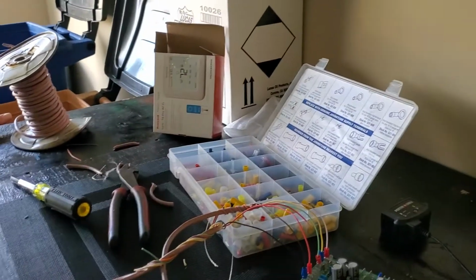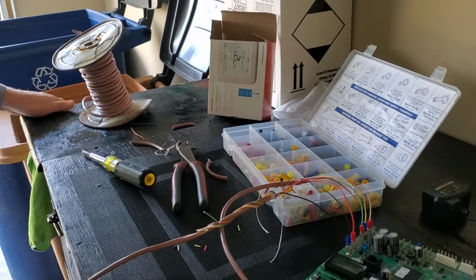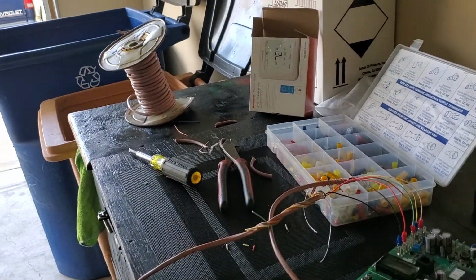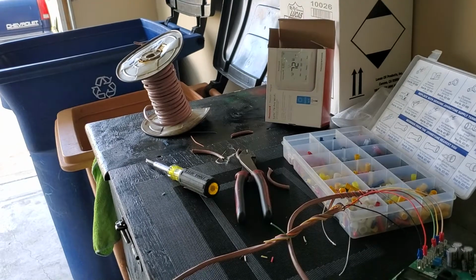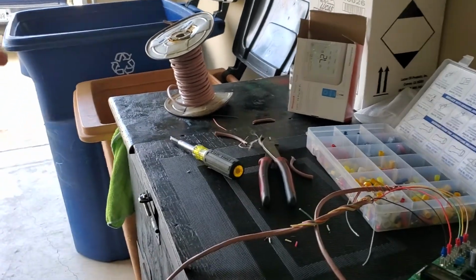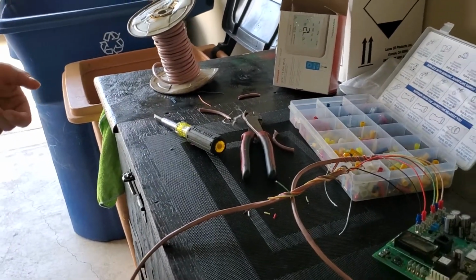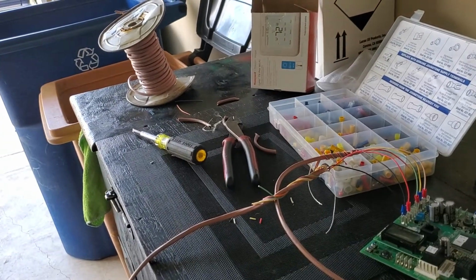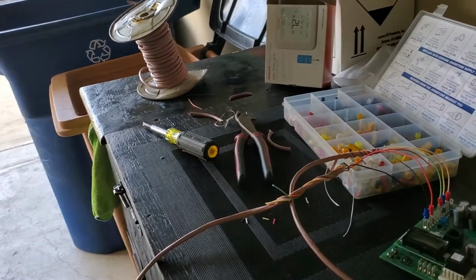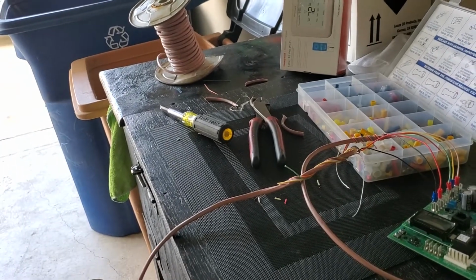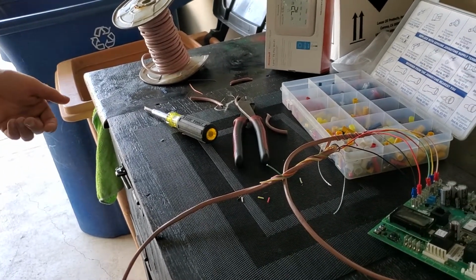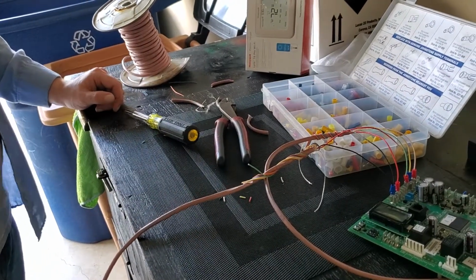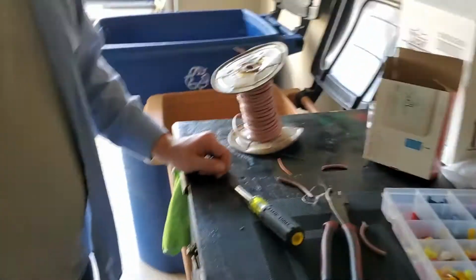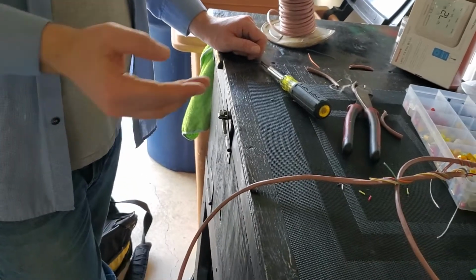Well, the way I might handle that situation is I would ask, is your thermostat on, is the thermostat lighting up? That's as far as you went. If the thermostat's on and lighting up, now it can shut off for other reasons - they have a big pan underneath the air handler, and if it starts leaking water, the float switch trips it and the thermostat might turn off. There could be other reasons why the thermostat might be off, but that would be my first question: is your thermostat on, is it lighting up? If it is, at that point, it's not your problem.